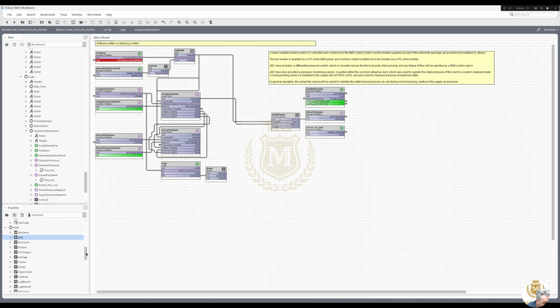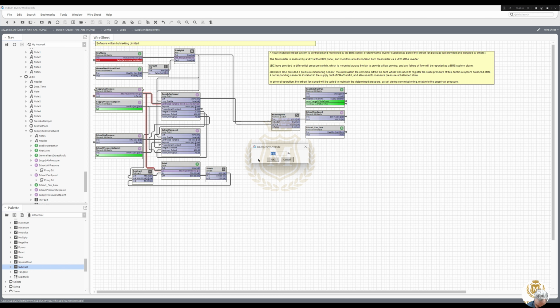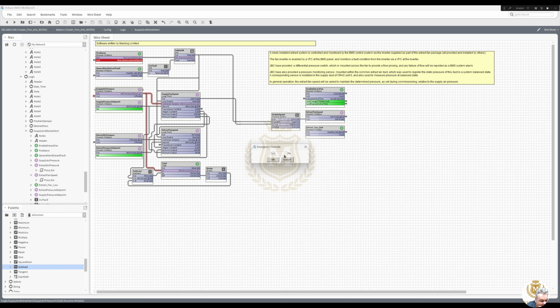Delete, subtract, pressure, take away. Let's try that again now. Actions, emergency override, let's put it to something stupid like 900. That's false. Actions, emergency override, put it to 700, so it's low now. We're increasing the speed. 700, so control variable, oops, what's that one there, is 700 and 80. So why isn't my speed increasing?